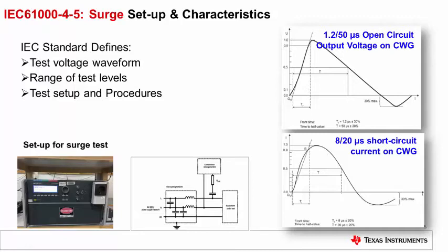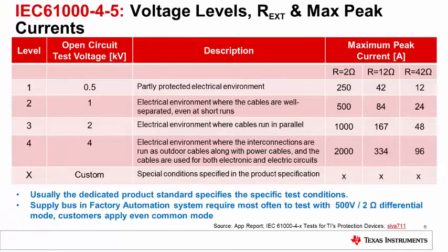The IEC defines the surge test voltage waveform, the range of test levels, and the test setup and procedures. The surge open-circuit voltage waveform has a 1.2 microsecond rise time and 50 microsecond half-wave time, while the current profile is defined by an 8 microsecond rise time and 20 microsecond half-wave time. The surge test has several test levels from Level 1 to Level 4, along with various coupling impedances.